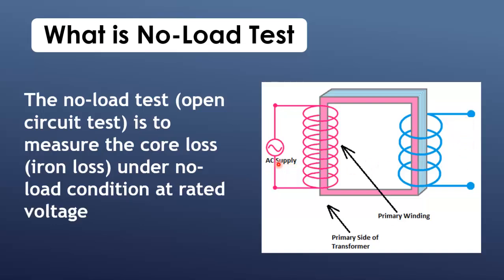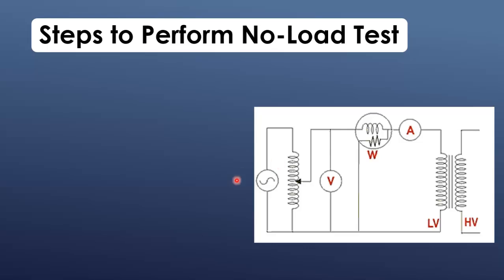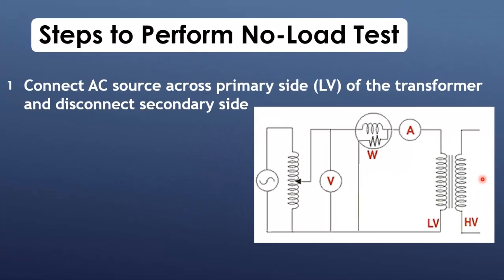Now we see how to perform no-load test of transformer. Connect AC supply across primary side or low-voltage side of the transformer, and disconnect or open the secondary side or high-voltage side of transformer.